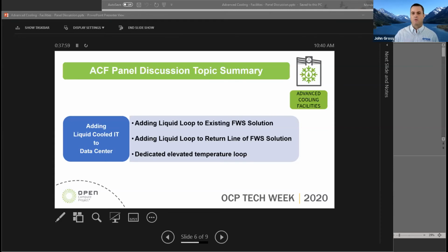Based on your workload and what market you're working with, you might see that with liquid cooling the temperatures are going to go up and up, and you can use more heat recovery. But in compute intensive workloads like HPC, the manufacturers are actually all predicting that the temperatures are going to start going back down. A lot of it has to do with the performance and the heat exchange across that case, and needing to get the fluid temperature colder in order to keep those processors cool.